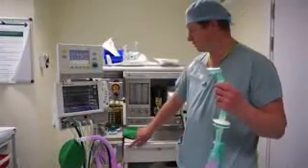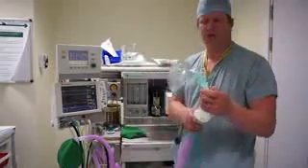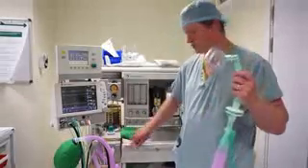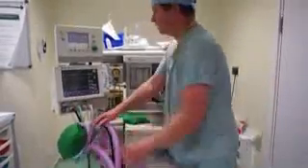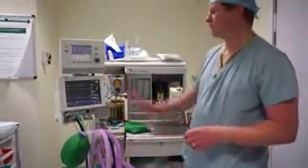We'll flip that back to the bag and get it left into a sensible state for our next case. I'm going to put the filter and mask back on. Then I'm going to check the oxygen flush and make sure there are no problems with this part of the circuit — I'm just going to feel and hear the air against my cheek as I press the oxygen flush, making sure all the connections are tight at both ends. The final test is to do the normal checks on the monitor to make sure the settings are as we want them. We're going to check the suction, turn the suction on, and make sure you've got a clean Yankauer.